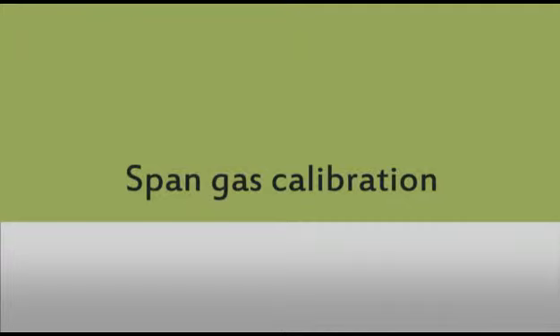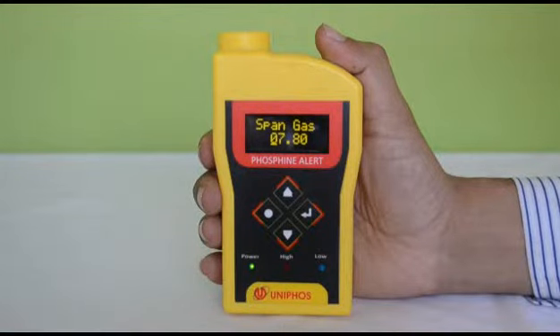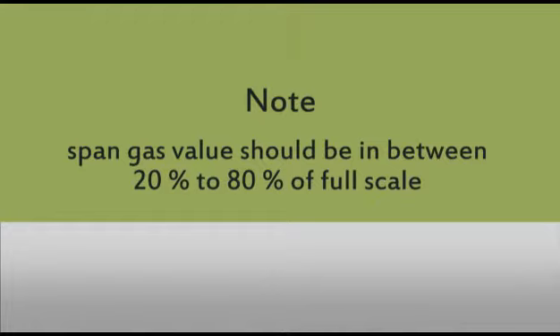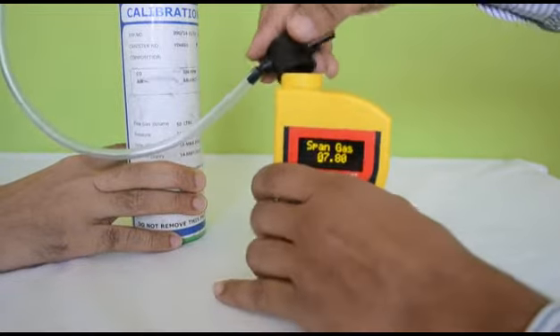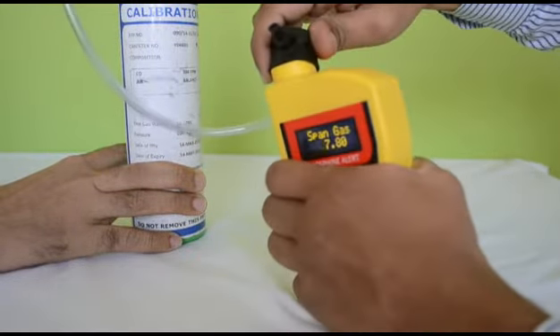Span gas calibration. On successful zero calibration, instrument will ask for desired span gas value. Note: entered span gas value should be in between 20% to 80% of full scale, else will not be accepted by the instrument and instrument will once again ask for span gas value.